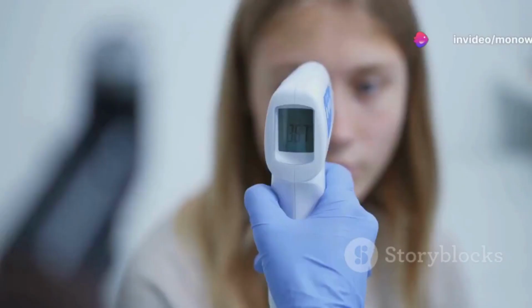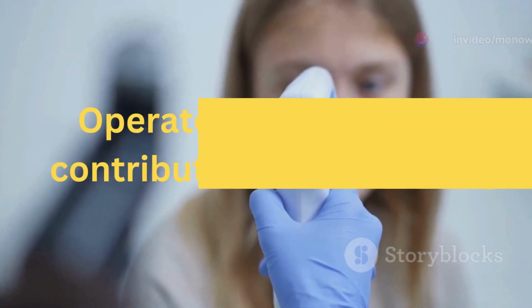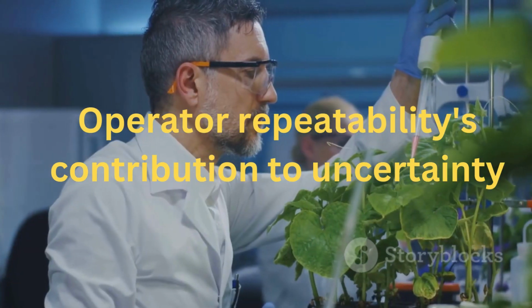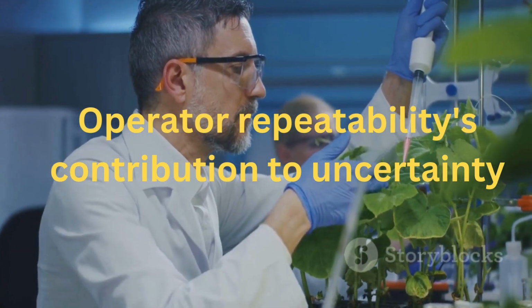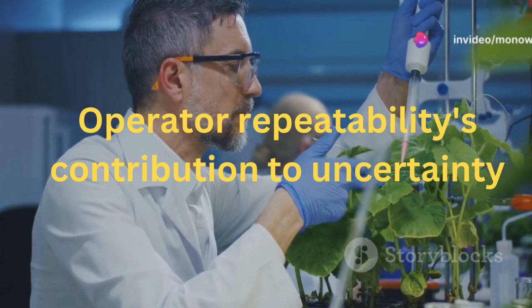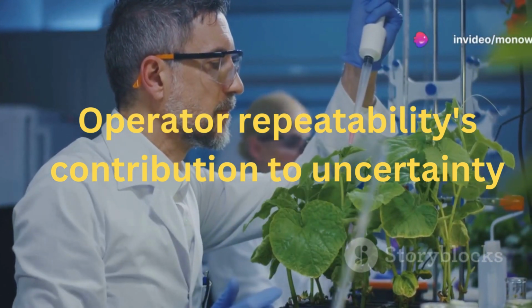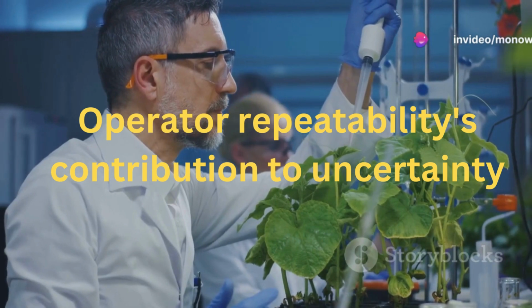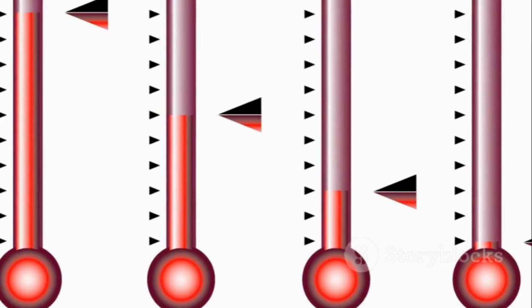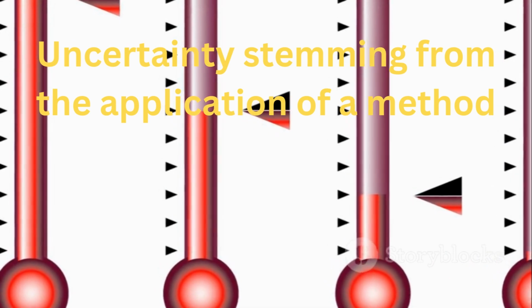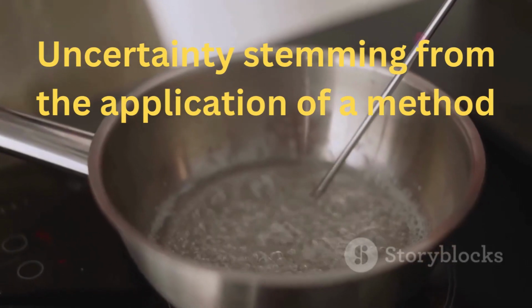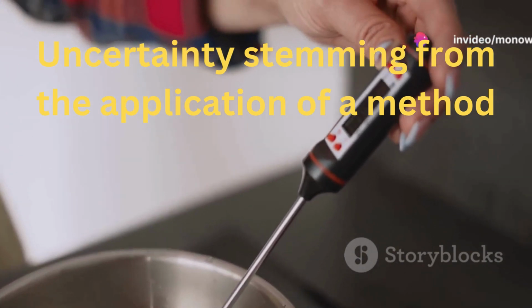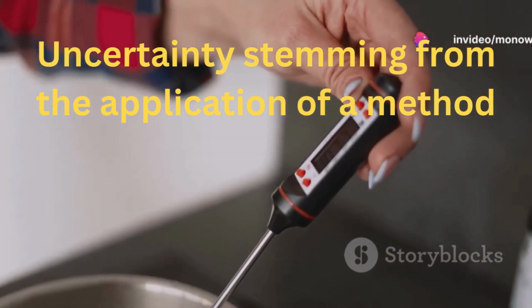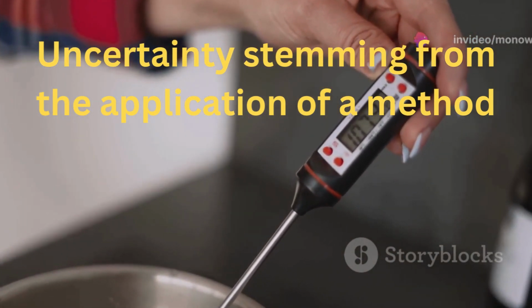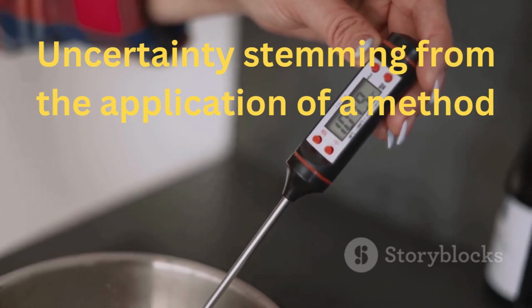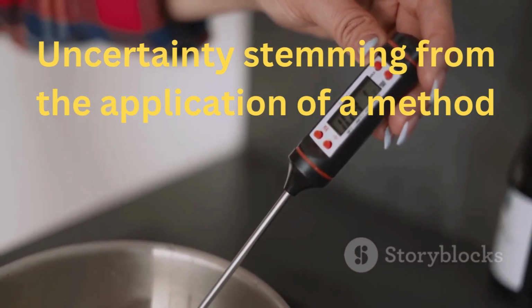environment. Human error is another significant source of uncertainty. Misreading the thermometer, misrecording data, or even mishandling the thermometer can all lead to inaccuracies. It's crucial to have well-trained personnel carrying out the calibration to minimize such errors. The calibration method used is also a fundamental source of uncertainty. Different methods may yield different results due to the inherent uncertainties in those methods. For example, comparing the thermometer to a reference standard might introduce uncertainties related to the reference standard's accuracy.